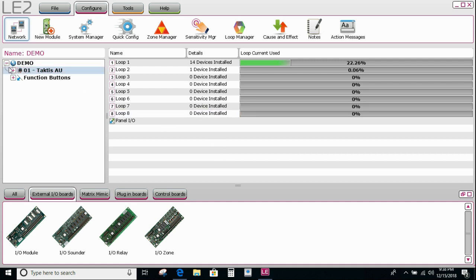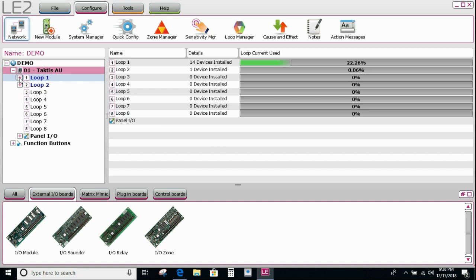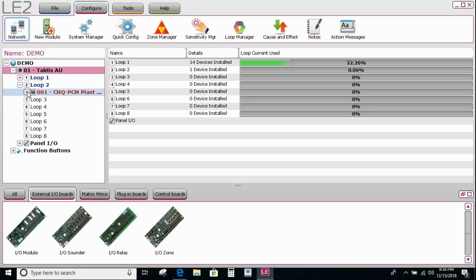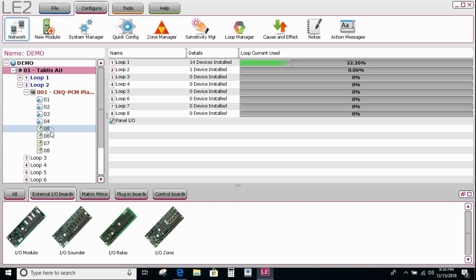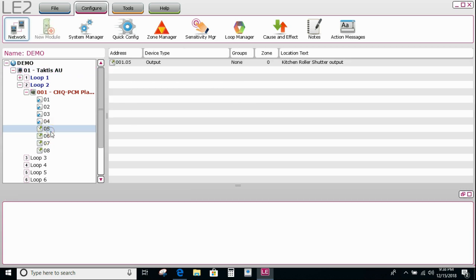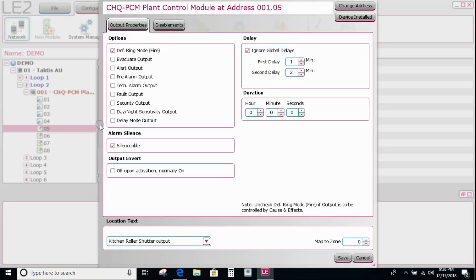To achieve that we need to firstly find the device itself — the output device that's going to be connected to the roller shutter. We need to then edit its attributes and untick the default ring mode. If I leave that on, it means this output will operate under any type of fire detection, so any input or any device that is marked up as fire would operate it if I left this box ticked.